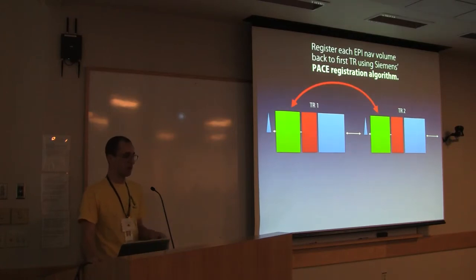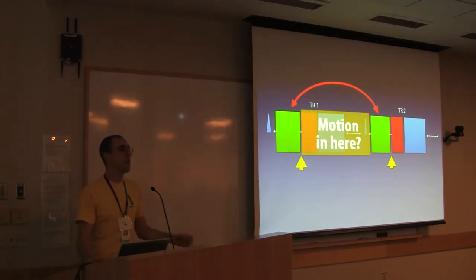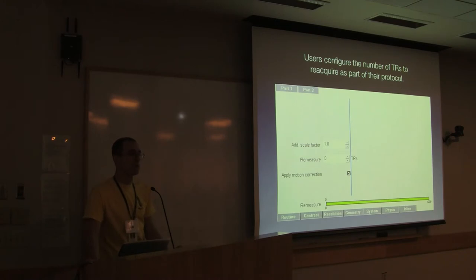We're registering during each TR. Each TR is two to three seconds depending on the sequence you're running. We take a navigator and we register it back to the first one. The instant when we have exactly right coordinate spaces is immediately after the navigators. That's when I've got my coordinates exactly right. But what if the person moves in all that huge gap in between? Well, we don't see that motion during that time. We're blind to that motion. We can't correct it. We can only correct for the frequency of every two or three seconds. That leaves us vulnerable to motion in there. What we do is we reacquire those motion damaged TRs. We can detect that the person moved in there because they're in a different position when we reached the end of that block than they were at the beginning.